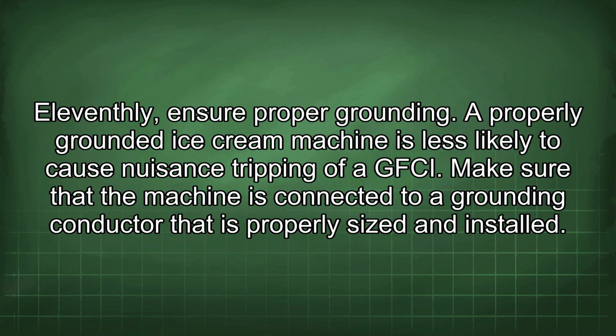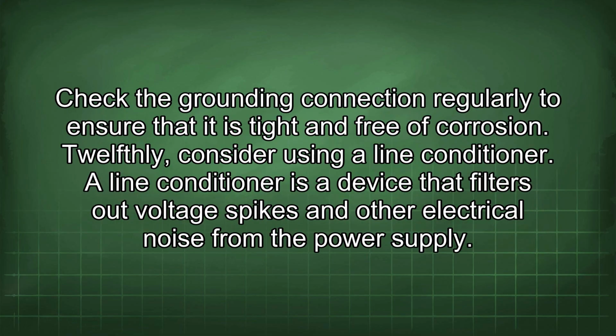11thly, ensure proper grounding. A properly grounded ice cream machine is less likely to cause nuisance tripping of a GFCI. Make sure that the machine is connected to a grounding conductor that is properly sized and installed. Check the grounding connection regularly to ensure that it is tight and free of corrosion.